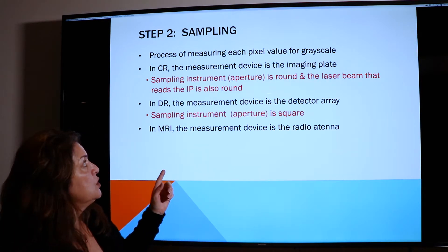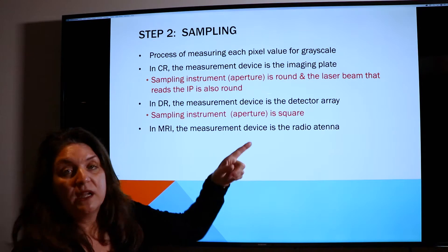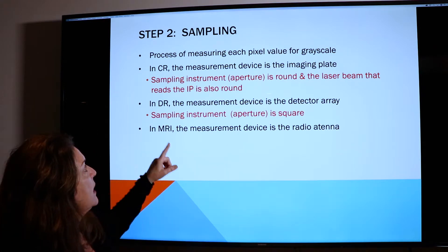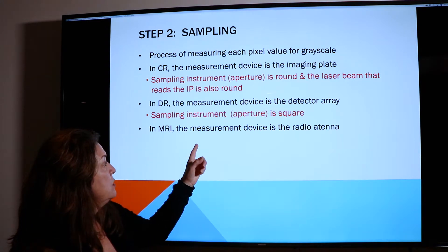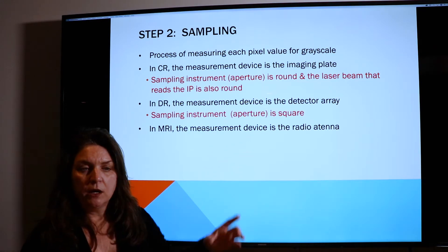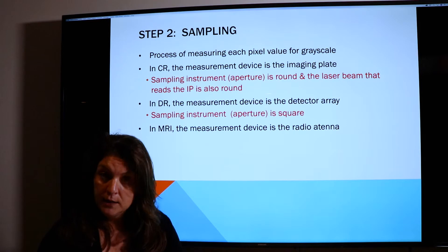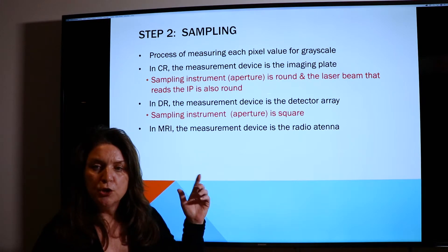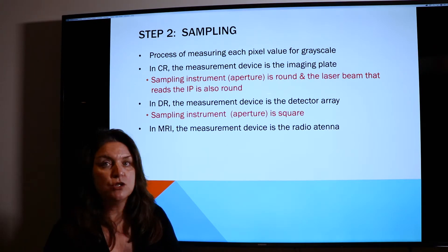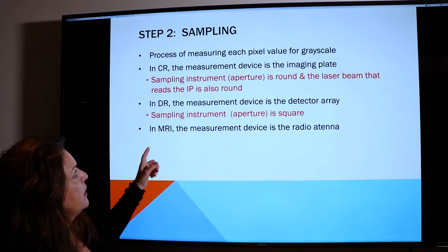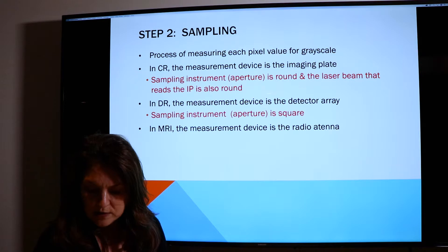The sampling portion is where an instrument actually measures the pixels and the grayscale level. The sampling instrument for CR is round. The sampling instrument used for DR is square, and that's important because in DR our detectors are square or rectangular, and the monitors are rectangular. So you get more detail because the measurement tool is square, matching all the pixels, which are also square. Sampling just measures each pixel for its grayscale.